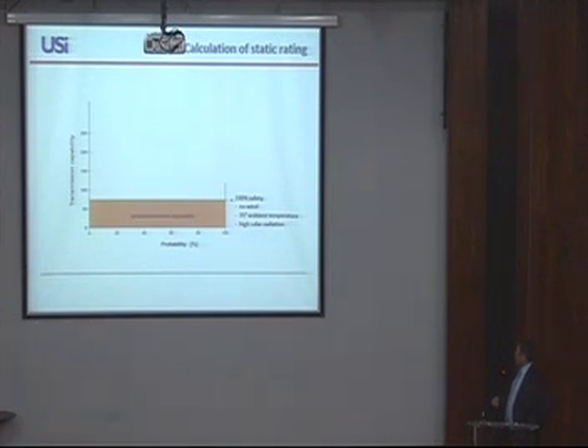If you make these conservative assumptions, you can use the heat balance equation from before, and that provides you with a value for the current, or the capacity, of a line. And if you use that capacity for operational purposes, 100% of the time you are safe. Never a problem. But this is too conservative, especially with no wind. We know there's always a little bit of wind, and even at 0 wind speed you have some convection. So the designers came up with a value, and this is a funny story how it came about, because it had no physical background, but it is used all over the world today.